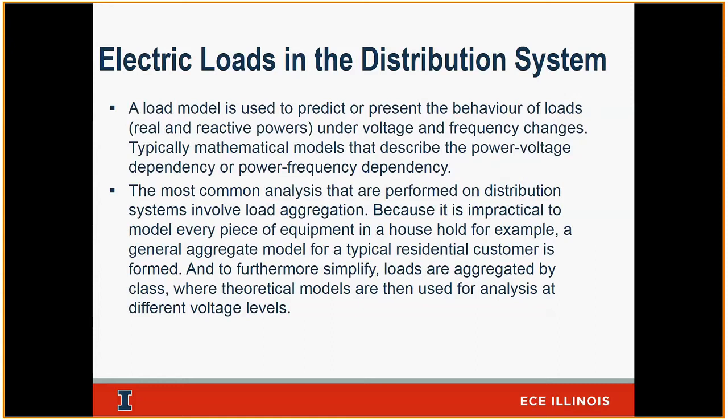So we'll do a lot of research. We'll talk to a lot of manufacturers. We'll better understand what a typical zip model for a fridge would be, what a typical zip model for an oven would be, for a fan would be. And then we would know what a composition of a house would look like. Then if 80% of my load is going to be residential, then I know what my load is going to look like for 80% of my circuit.